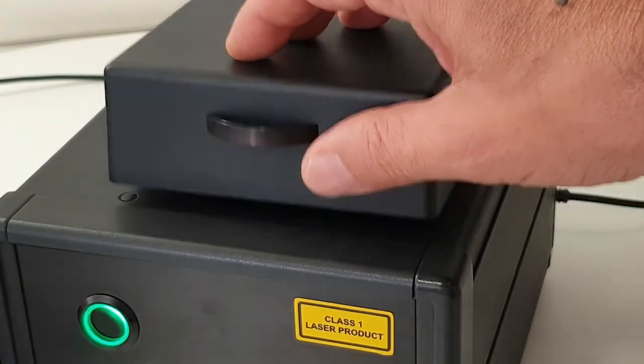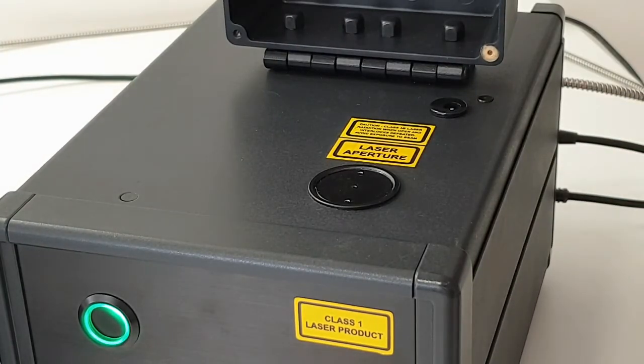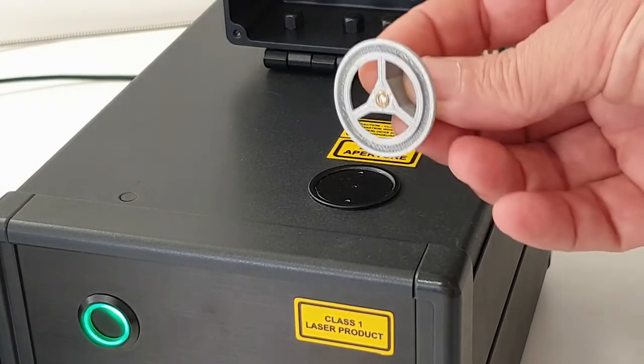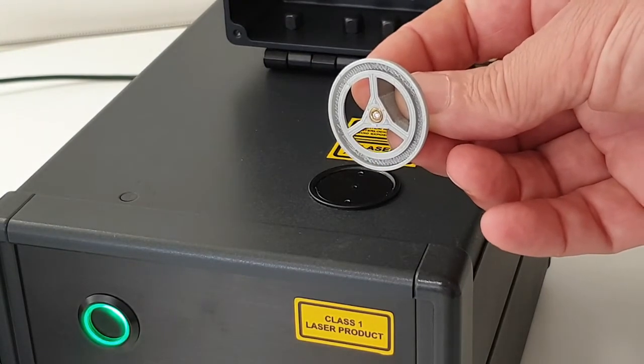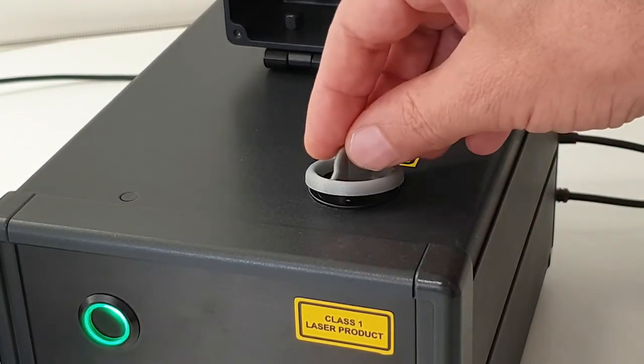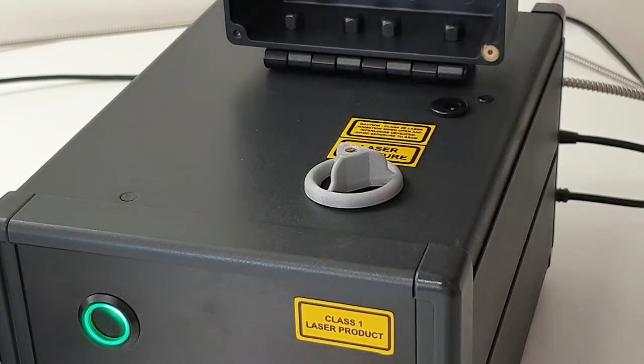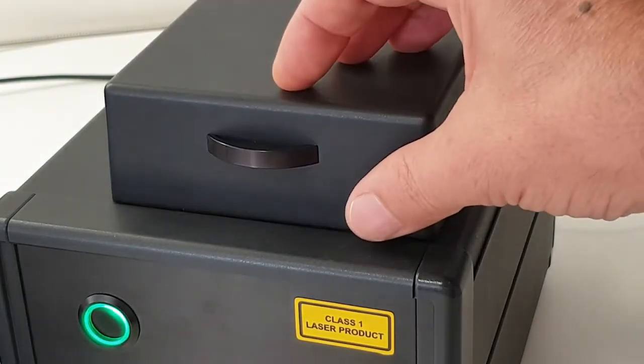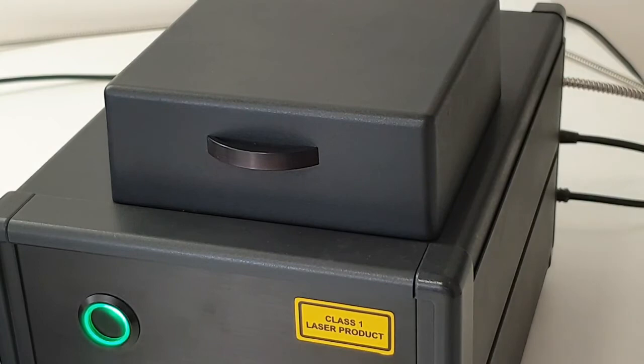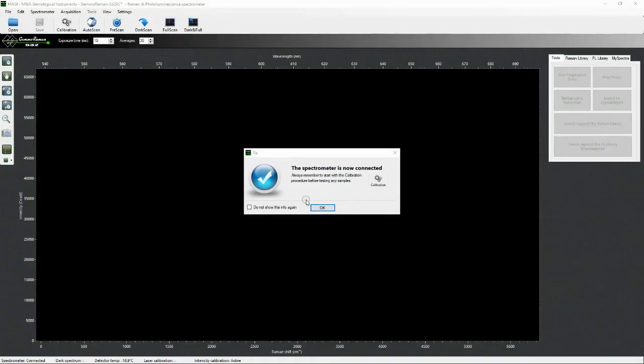Open the sampling chamber and put the calibration piece provided at the center of the sampling disk. The piece features a small diamond in the center which will match with the sampling disk aperture. An auto-centering frame will ensure the correct alignment of the calibration piece. Close the sample chamber. Click on the calibration icon of the pop-up window.